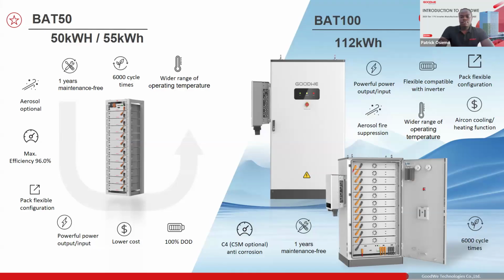Now with the hybrid inverters I've just presented, these are the batteries that are compatible. We have two versions. The indoor version, which is the BAT50 or the BAT55, and we have the outdoor version, which is the BAT100. Now, the only difference, apart from the capacity levels, is the functionalities. The BAT50 is an indoor battery, so you have to put it in a constrained, monitored environment in terms of temperature, humidity, and dust, while the BAT100 is fully outdoor. So you basically can mount it outside. It has an inbuilt AC for both cooling and heating. It has a dehumidifier and all that. So in case you're doing outdoor installation, then you'll be checking the BAT100.